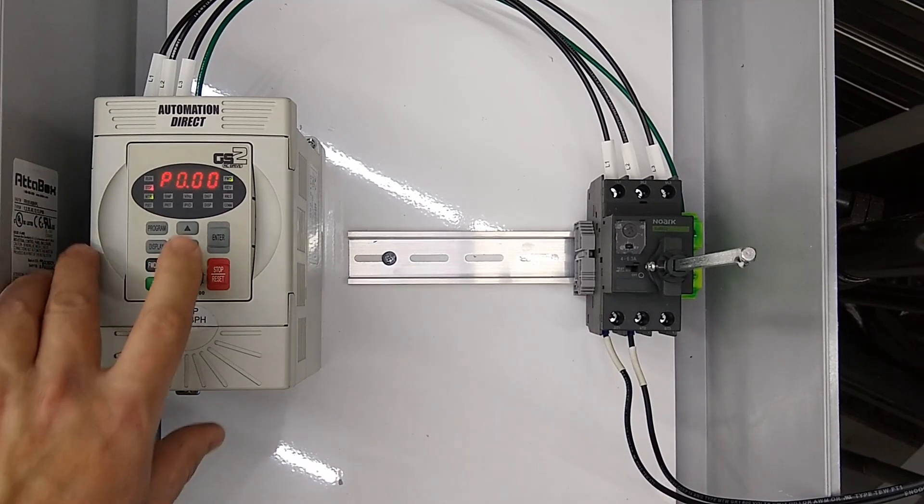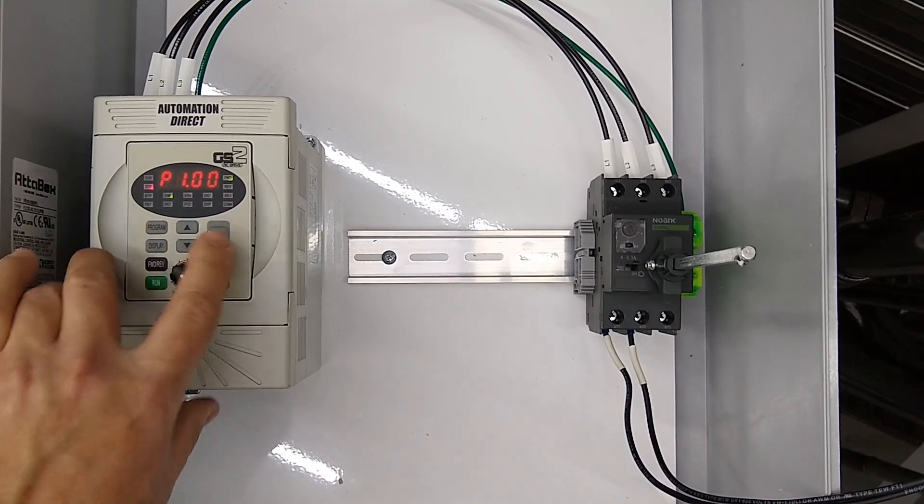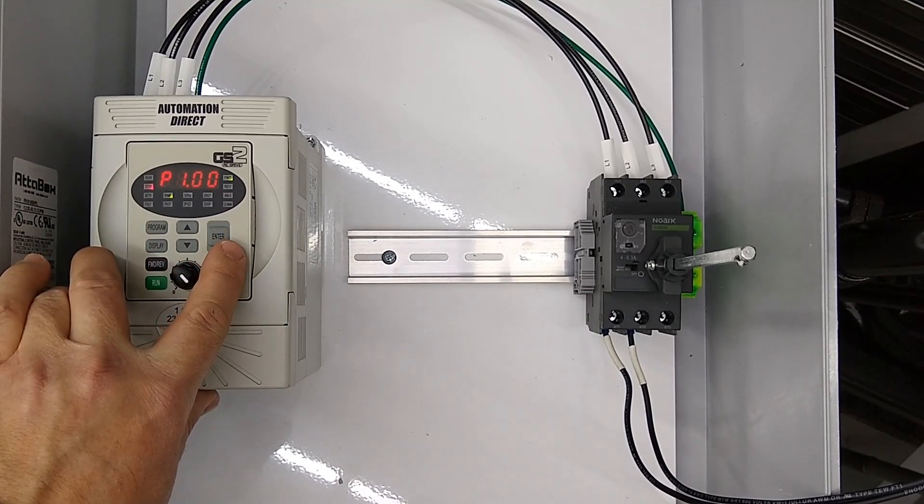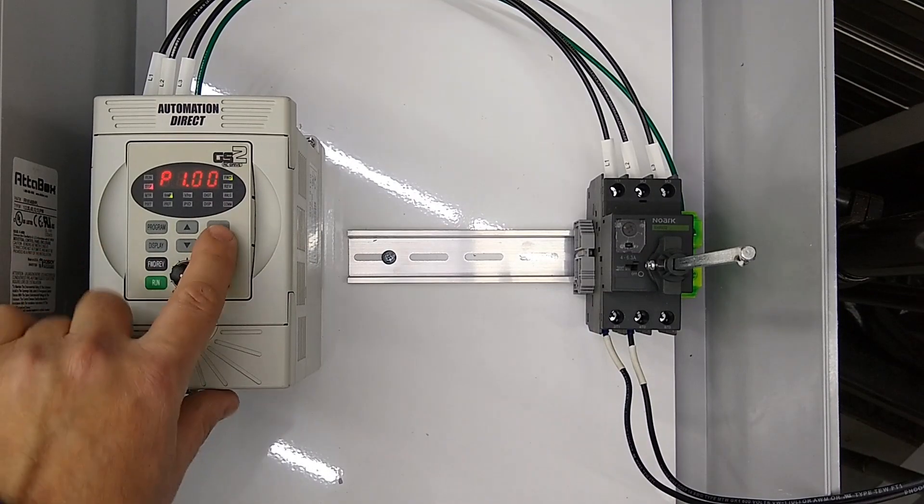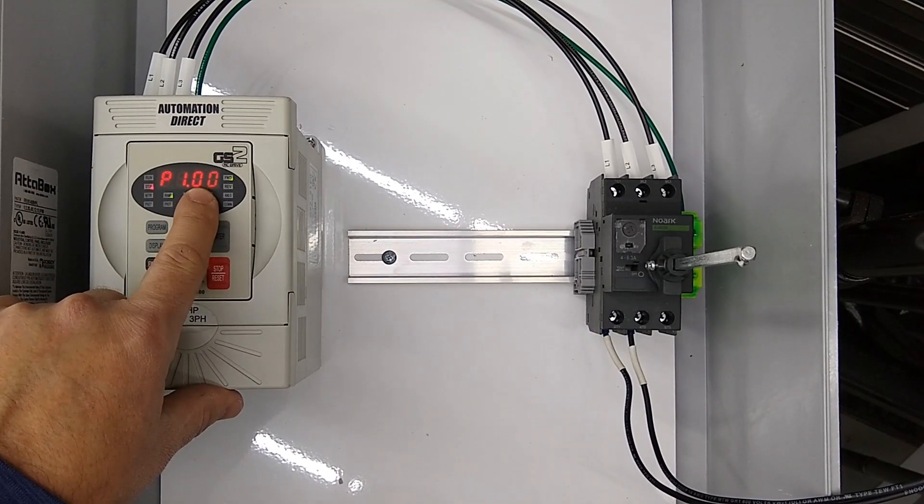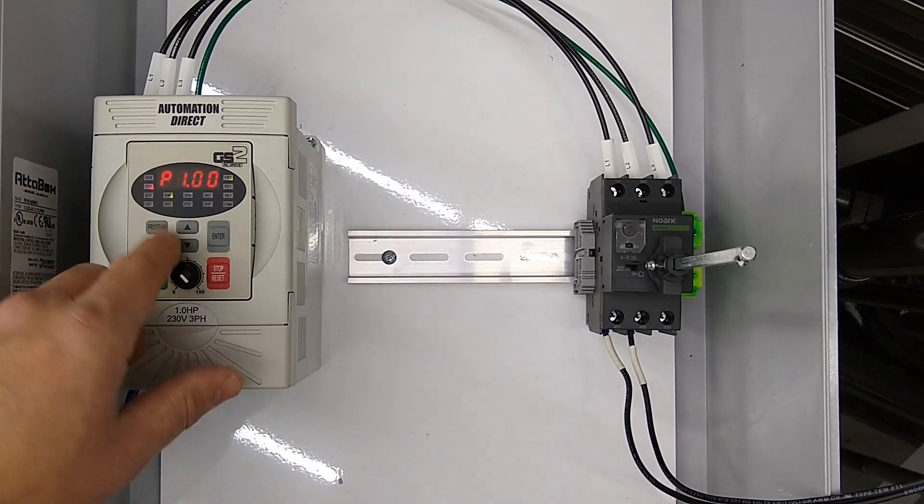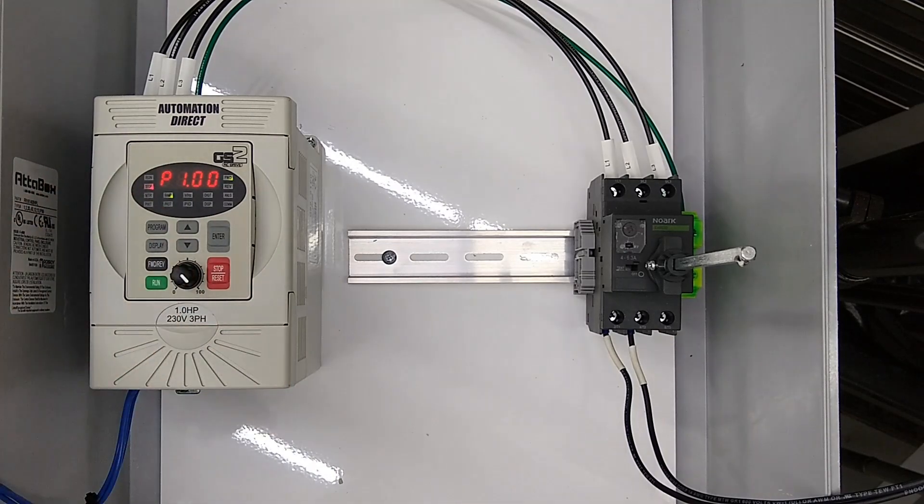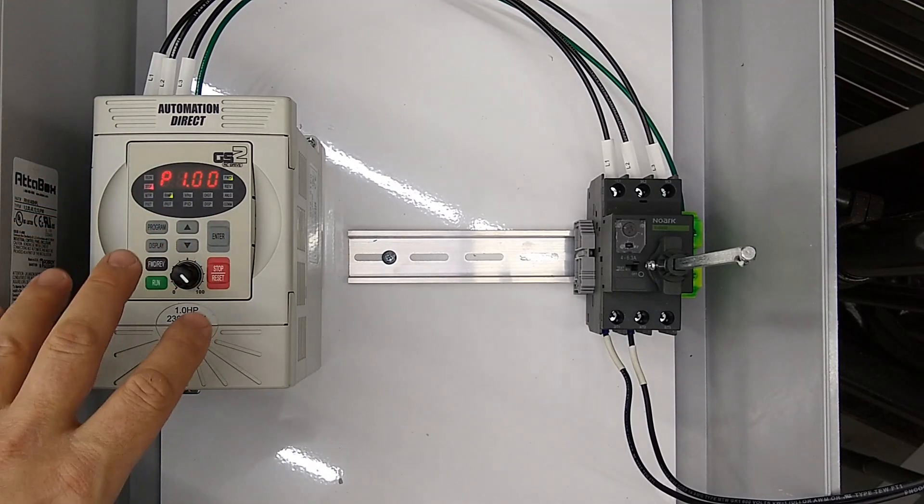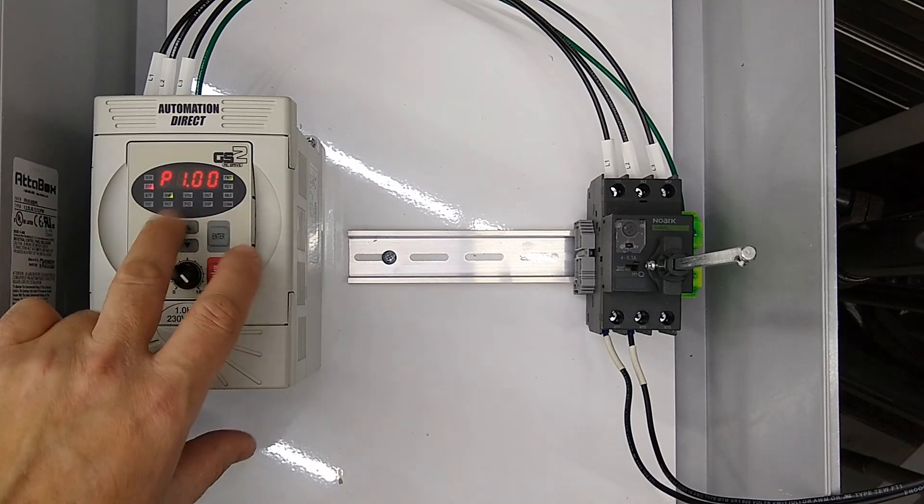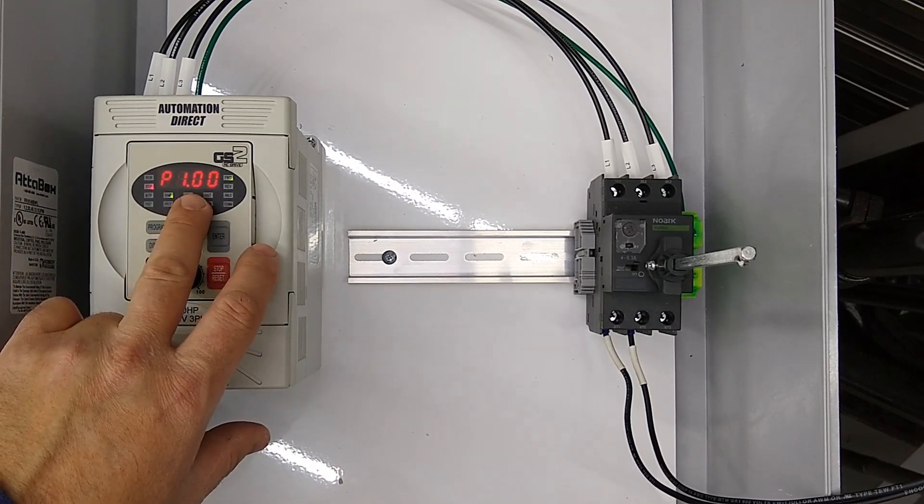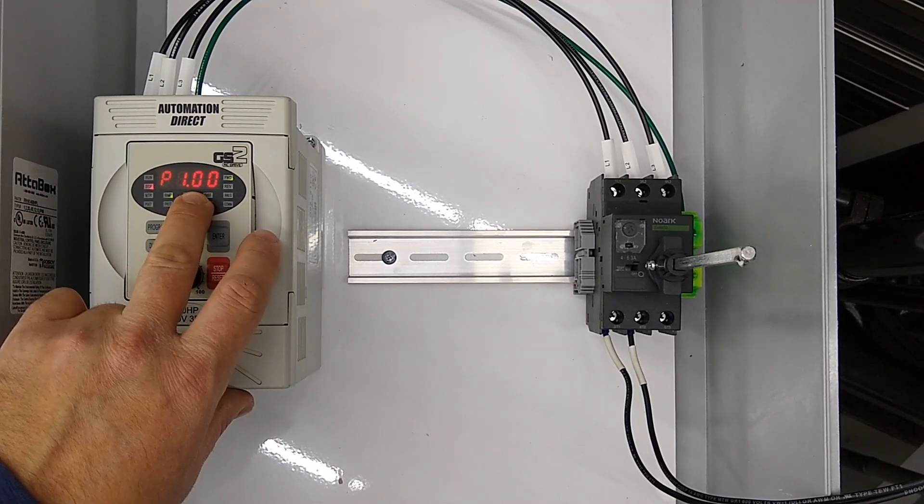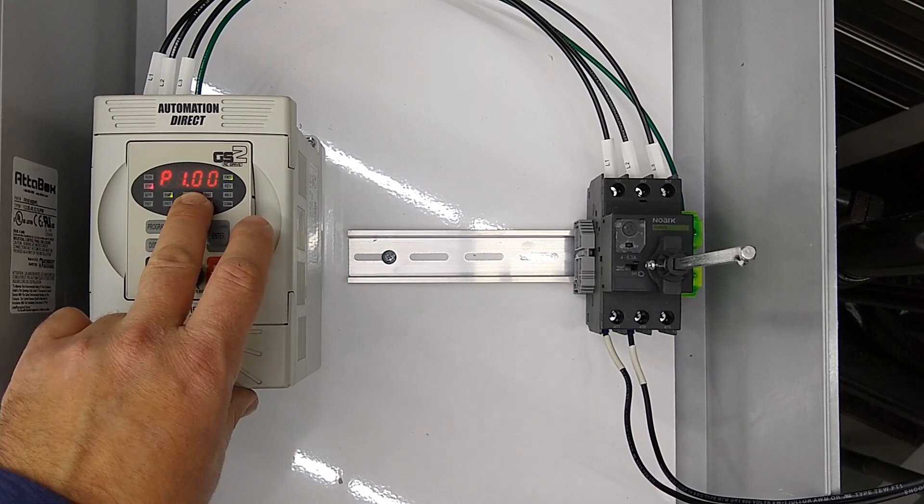If you hit the program button until it comes up with p1.00, this one is going to determine your stop method. By default it's going to ramp to stop, which means it's going to come to a controlled stop over a set amount of time. If you set this to one, it'll make it coast to stop, which is useful in a lot of applications.